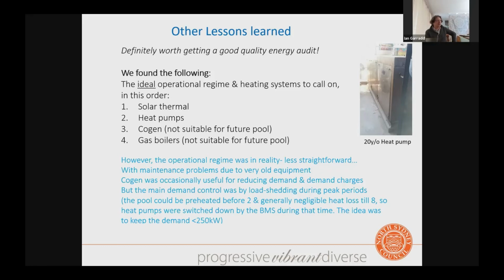Another critical point about running a pool in terms of cost of operation: it's really important to keep the electrical demand to a minimum, especially during peak periods, which has been 2 p.m. to 8 p.m. in New South Wales on weekdays. By having demand control, we saved around $20,000 a year once we got the demand under 250 kilowatts.